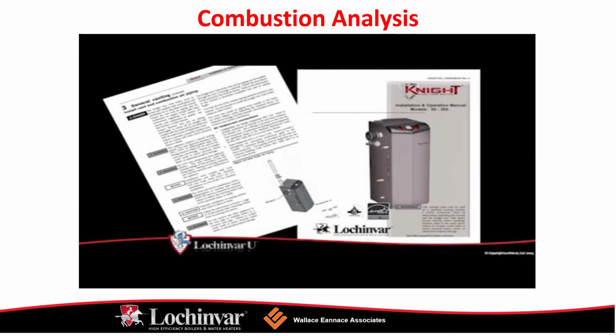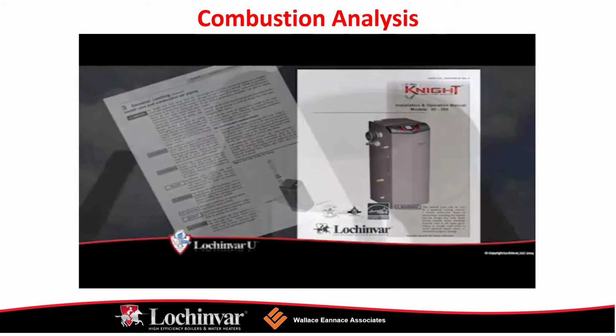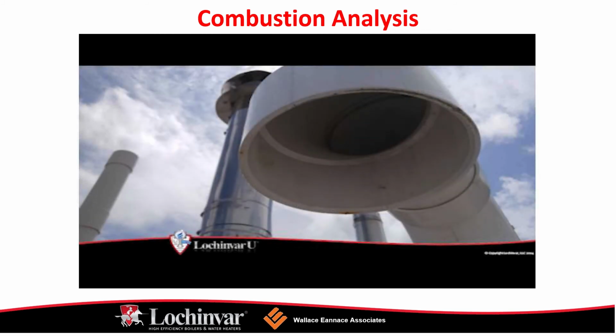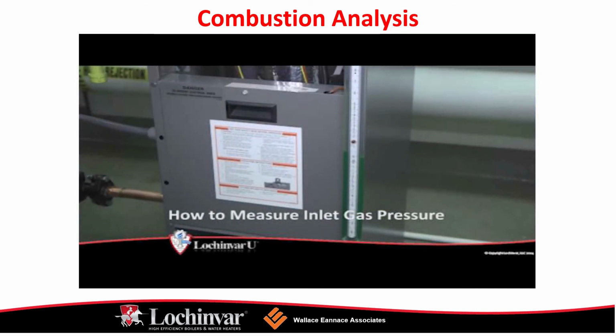Locate the pinhole button on the display. Using a paperclip or something similar, press and hold the button for 5 seconds. The word service will appear in the status line of the display. The unit will fire at its normal ignition speed and will then modulate its firing rate to 100%.